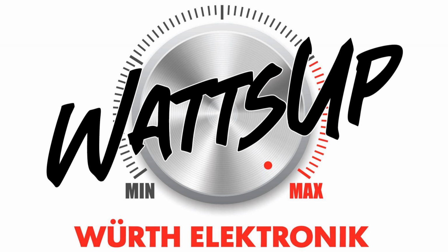So for mains filter chokes, mainline chokes, the limit is normally 70 degrees Celsius, because we have a maximum operating temperature of our components of 125 degrees Celsius. And for 55 Kelvin, then it's just a difference. So the rated current is defined for 55 Kelvin self-heating, and so I have to reduce if I go above the 70 degrees.